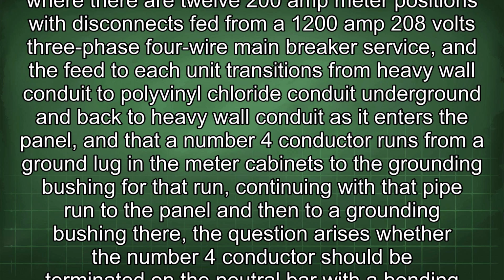Now, to address a specific installation scenario, where there are 12 200 amp meter positions with disconnects fed from a 1200 amp 208 volt 3-phase 4-wire main breaker service, and the feed to each unit transitions from heavy wall conduit to polyvinyl chloride conduit underground and back to heavy wall conduit as it enters the panel, and that a number 4 conductor runs from a ground lug in the meter cabinets to the grounding bushing for that run, continuing with that pipe run to the panel and then to a grounding bushing there. The question arises whether the number 4 conductor should be terminated on the neutral bar with a bonding strap or on a lug on the panel cabinet.